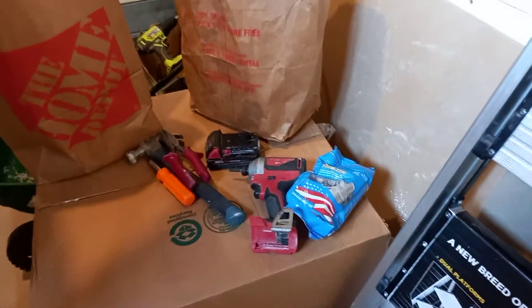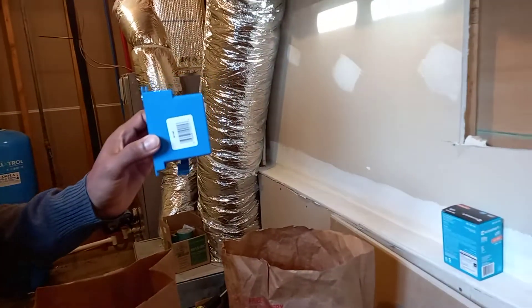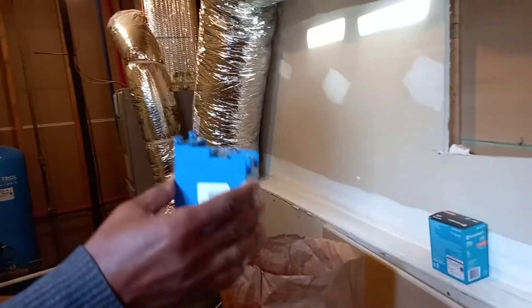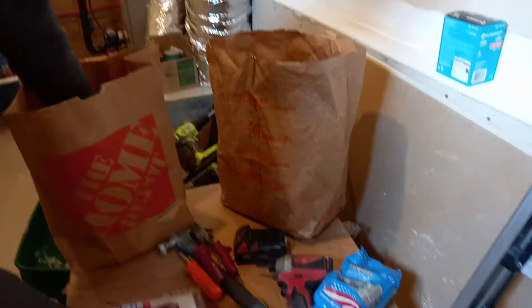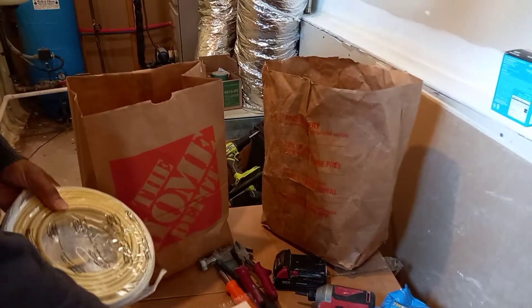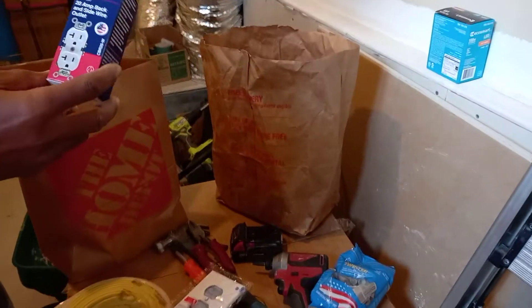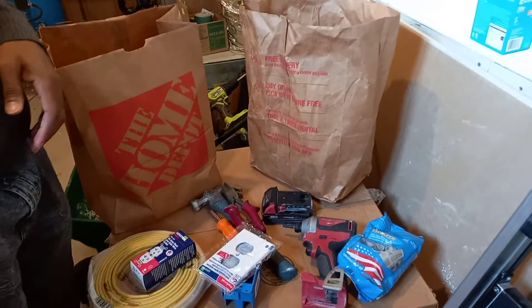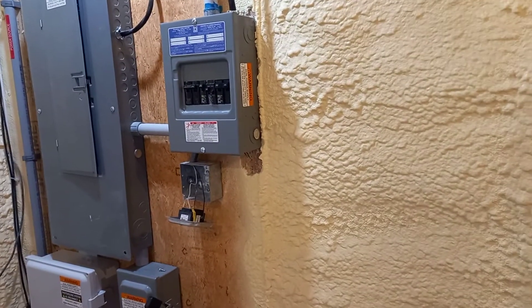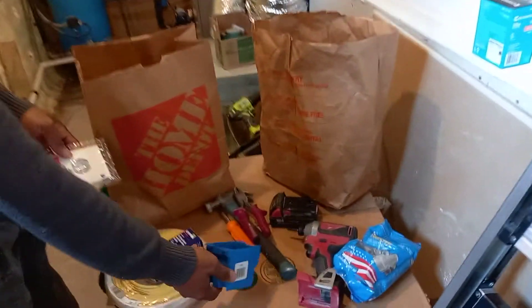For this project, we're going to use an old work box that we'll put on the wall over there, 12 AWG American wire gauge cable, and a 20 amp outlet. Let's run the wire from this box to the laundry location and put up the old work box, then do the connections.